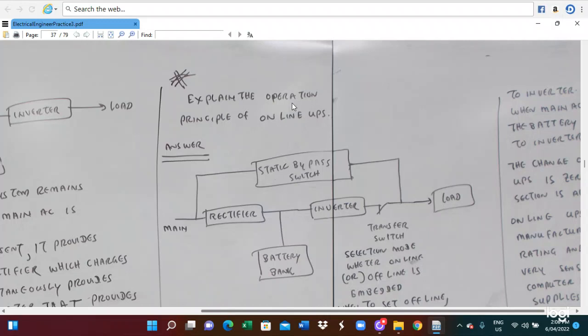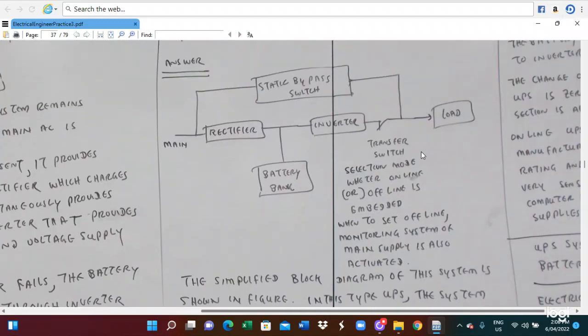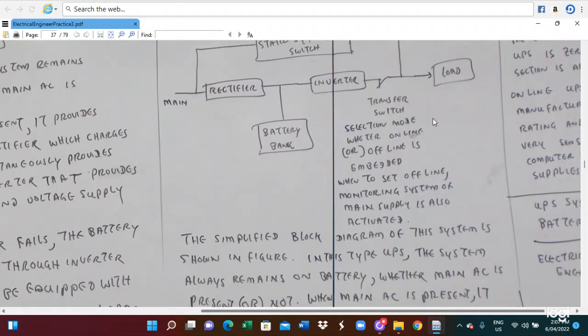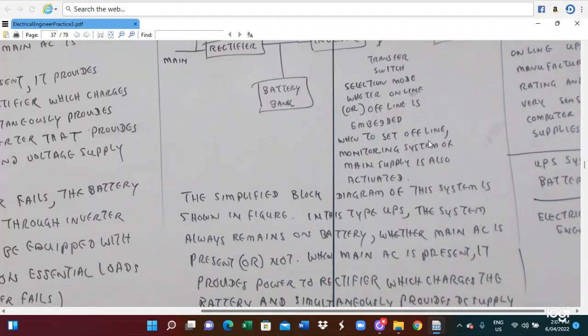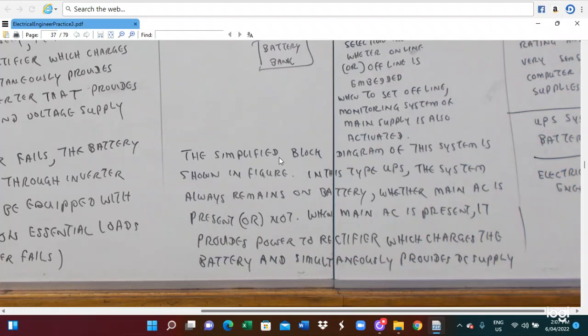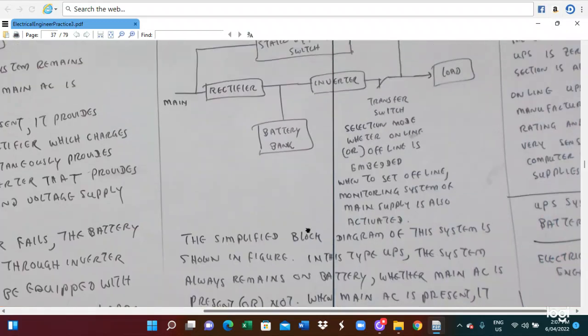Here is the operation principle of the online UPS. So this is the online UPS system. Here you see the main, rectifier, inverter, battery bank, static bypass switch, and the connection to the load. This includes the transfer switch. The transfer switch selection mode is whether online or offline is embedded. When set to offline, the monitoring system of the main power is also activated. The simplified block diagram of the system is shown in the figure. In this type of UPS, the system always remains on the battery, whether the main AC is present or not. When the main AC is present, it provides power to the rectifier, which charges the battery and simultaneously provides the DC supply.